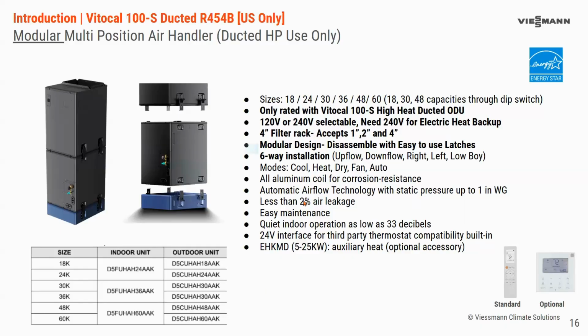It is 120 or 240 volt power selectable, calling out that if you're using the electric heat kit, you will need a 240 volt power source. So that 120 volt allows you to swap this in where a furnace was before. So the dimensions of this are geared towards a furnace replacement. It's a little narrower than the previous unit. This filter rack accepts 1, 2, or 4-inch filters.